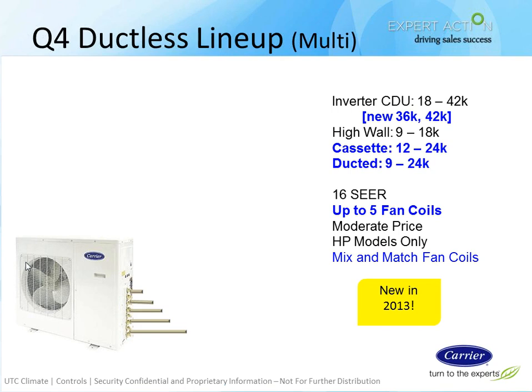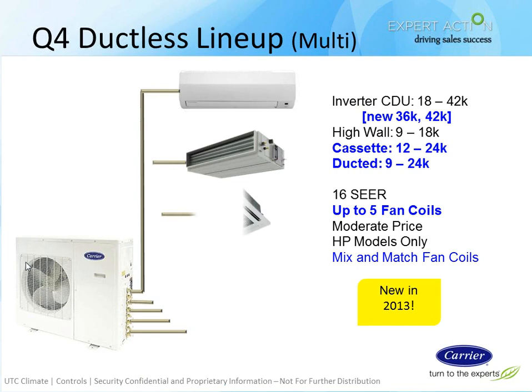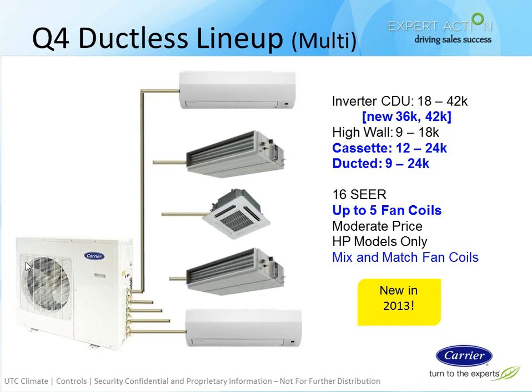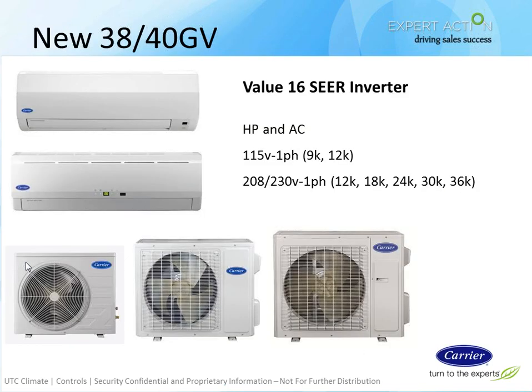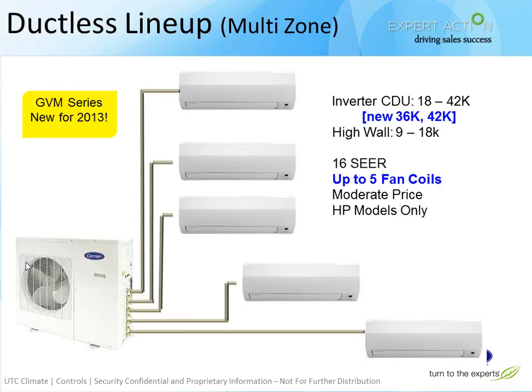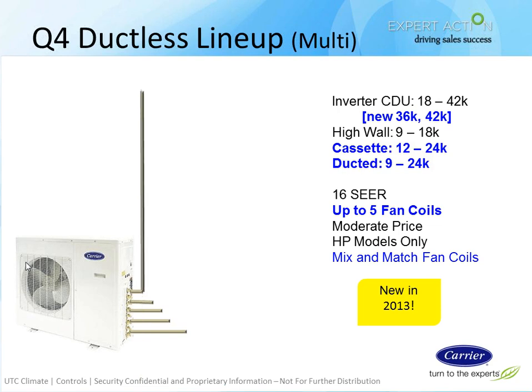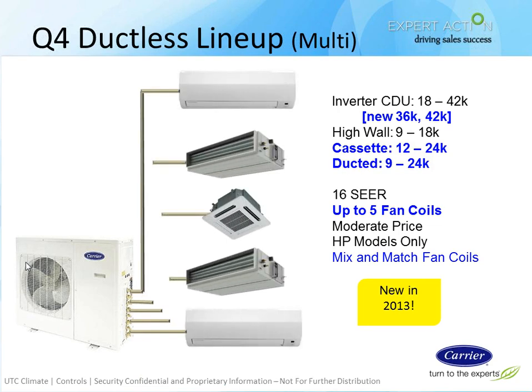Another new development for 2013 is a GVM with additional indoor units. We have the high walls, ducted, and we have ceiling cassettes as well. You'll be able to mix and match these different types of indoor units, again with that 130% indoor connected capacity. I apologize for the piping. It just didn't work this time, but it is piped much like the system I showed before. I'll go back to that for a second. We have 5 sets of ports there on the outdoor unit on the left, and you must pipe home run to each of those indoor units. And there it goes, sorry.